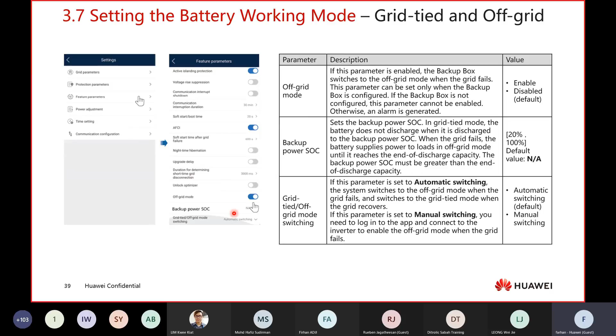Okay, this is how to set the battery mode for off grid. Your guys may ask, how can the inverter go to this mode? Actually the trick is in off-grid mode. In the setting, when you go to grid mode, they have this function. Make sure that without the battery, this function cannot be used. Only when you configure with the battery will this function appear.